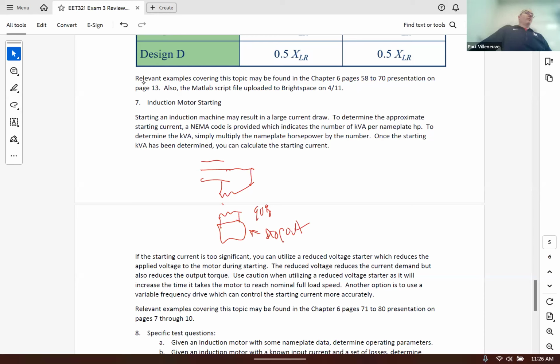Also, there's some requirements about the National Electric Code. I'm not sure how much the National Electric Code applies to motor starting, but there's a rule, 3 to 5%. But if you're starting a motor, I think you can go up to 10%. And after that, you have to change it out. So one of the ways to do it is you can buy bigger wire, right? You can reduce the impedance. Problem is that's very expensive. That means more copper, which ain't cheap.